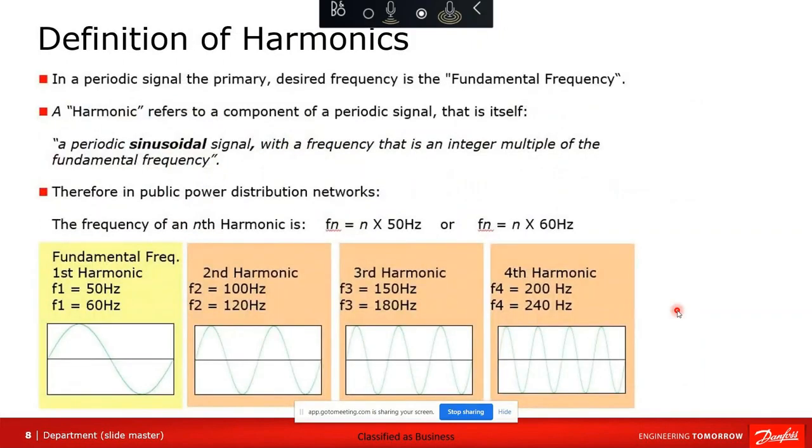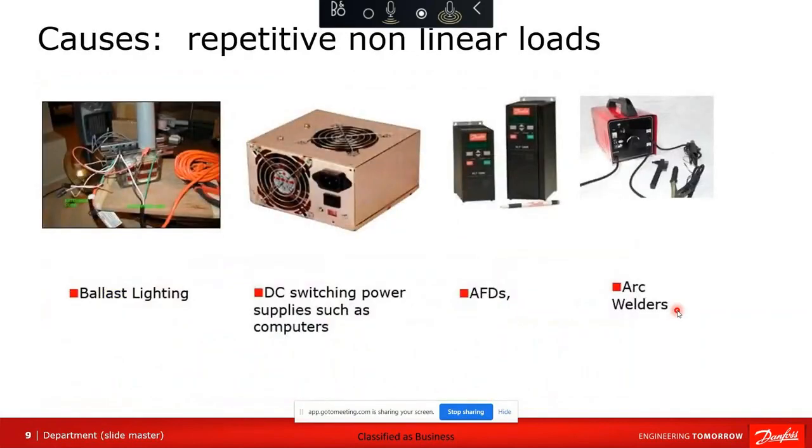So that's where the problem comes in. For the most part, we've not really seen catastrophic failures as a cause of harmonics. You can overheat transformers, and if you overheat a transformer to a given degree, yes, you could blow it up or catch it on fire, which would be a catastrophic failure. But we haven't seen anything so horrific that this has been such a devastating problem. However, there are concerns in the plant.